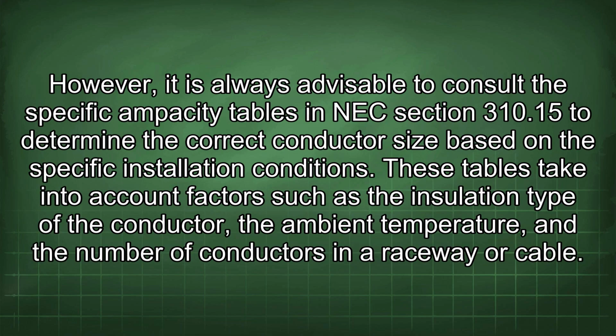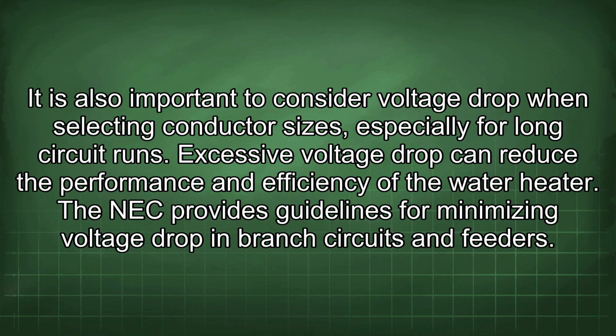However, it is always advisable to consult the specific ampacity tables in NEC section 310.15 to determine the correct conductor size based on the specific installation conditions. These tables take into account factors such as the insulation type of the conductor, the ambient temperature, and the number of conductors in a raceway or cable. It is also important to consider voltage drop when selecting conductor sizes, especially for long circuit runs. Excessive voltage drop can reduce the performance and efficiency of the water heater. The NEC provides guidelines for minimizing voltage drop in branch circuits and feeders.